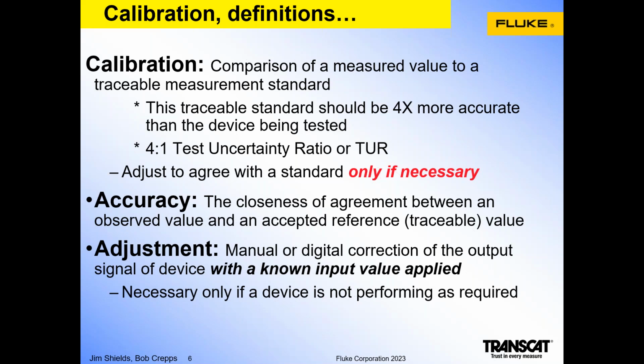Accuracy, the definition of accuracy, is the closeness of agreement between the observed value and the traceable accepted reference value. And then adjustment. Adjustments can be manual in the event of some of the old school analog instruments that had zero and span potentiometers that a technician would adjust their 4 and 20 milliamp signals with, with the application of a process signal on their inputs. But that technology is by and large being replaced by digital technology, the smart instruments that have digital corrections of the signal.